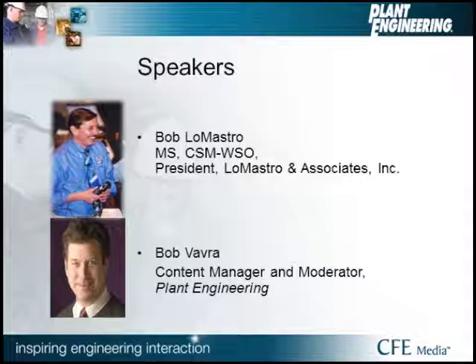Yeah, any equipment that sits over a period of time and doesn't go through any kind of maintenance, the risk of having a problem, the risk of an arc flash, is greatly increased. You're going to get buildup of dust, you'll get corrosion, and sometimes contacts can fuse or weld together. So even if you flip the handle of the breaker or of the disconnect and you think it's off, it's welded in the closed position. It's on. After an arc flash incident is the wrong time to be doing maintenance.